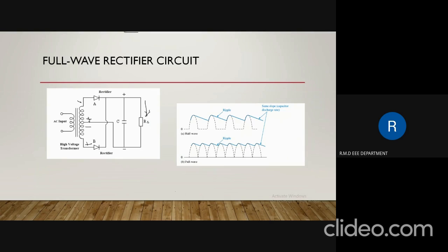So we are able to generate high voltage with the help of the half wave rectifier and full wave rectifier circuits. For high voltage applications of 50 kilovolt and above, rectifier valves are mainly used. In modern high voltage labs and testing installations, semiconductor rectifier stacks are commonly used for producing DC voltage. Mostly silicon diodes with a peak inverse voltage of 1 kilovolt to 2 kilovolt are used. For lab applications, the current requirement is less, so a selenium element stack with a peak inverse voltage of 500 kilovolt can be used.